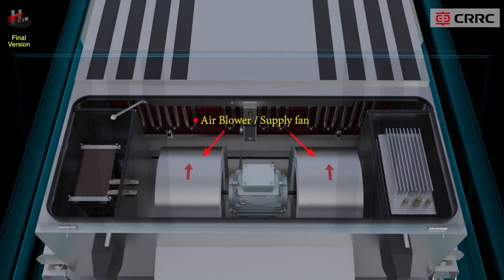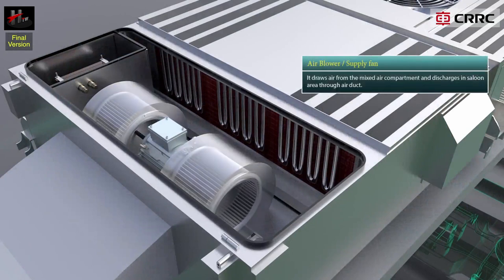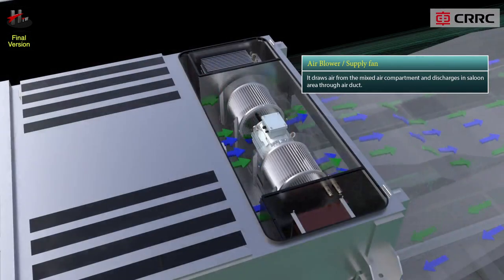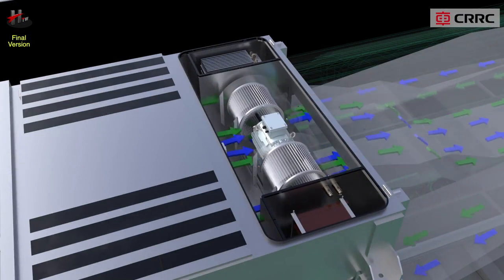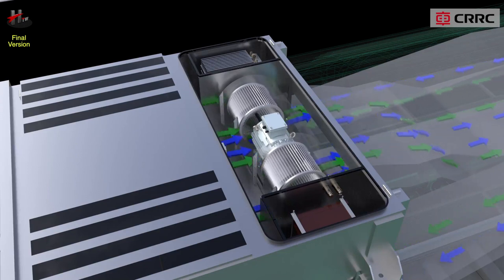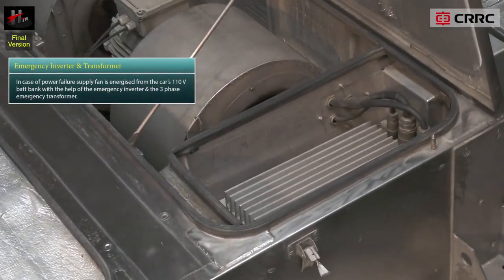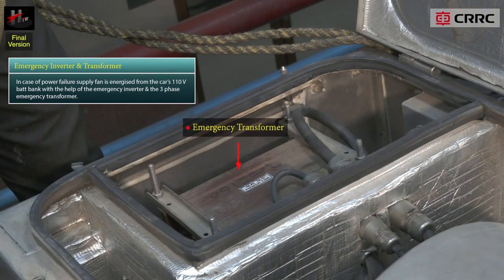The air blower or the supply fan located in the supply fan compartment is energized whenever the air conditioner is switched on. It draws air from the mixed air compartment and discharges it into the saloon area through the air duct. In normal operation the supply fan is supplied with 415 volts from the train's static inverter. In case of power failure, the supply fan is energized from the car's 110-volt battery bank with the help of the emergency inverter and the three-phase emergency transformer.